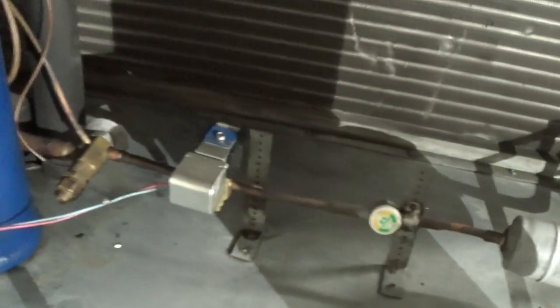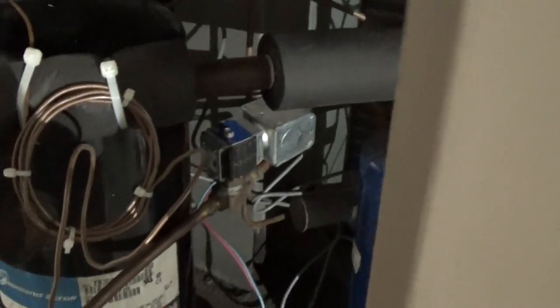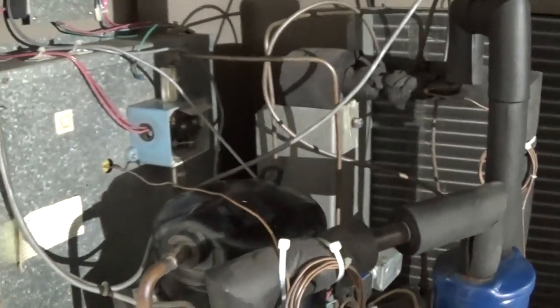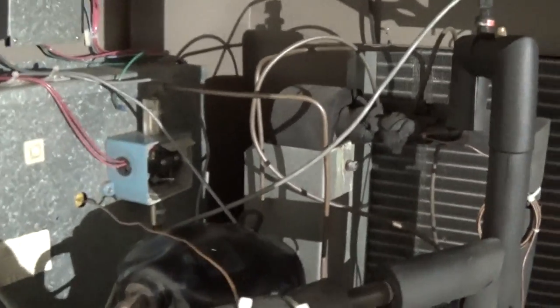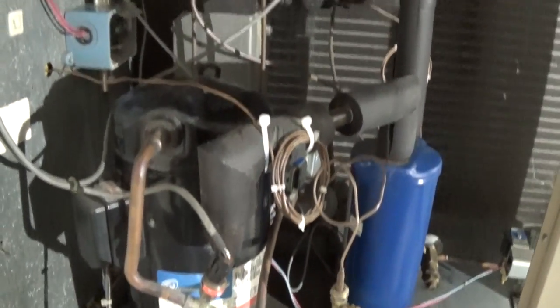Our solenoid positive shutoff here. This unit does have a hot gas bypass option. That's very important to mention. It's effectively a manually adjustable one. There's a knob back here. You shouldn't have to touch that. We have set that specifically for the running temperature of this unit, which is about 32 Fahrenheit. That also means you should run a 25 to 30% at least glycol solution in this chiller.